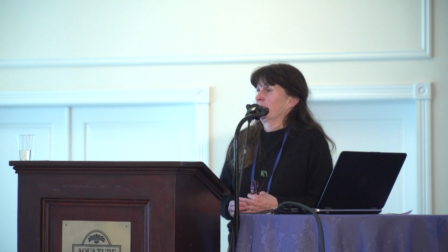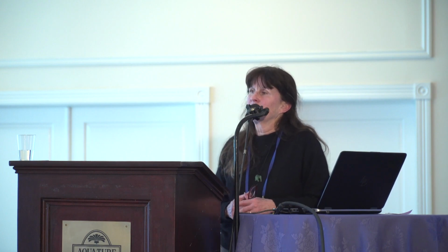Sometimes the pH, when it arrives in the lab, is a little low, and I would note that just in case in the future, if you do have an issue, I can go back and see how uncommon that was. Occasionally with chemistry too, somebody all of a sudden has selenium in their effluent and they haven't had it. I'll usually reach out and say, do you know where this came from? And that's just in case in the future it does become an issue.